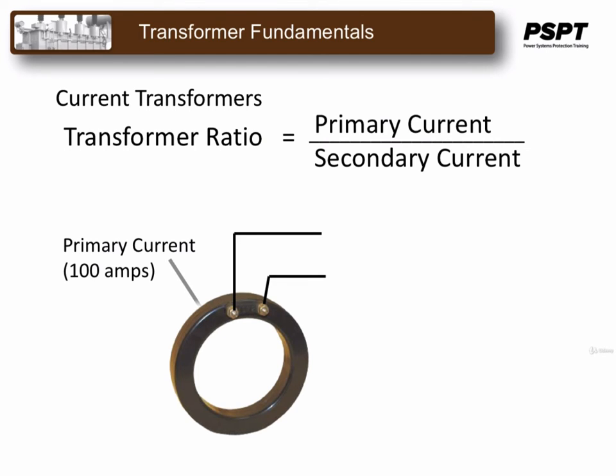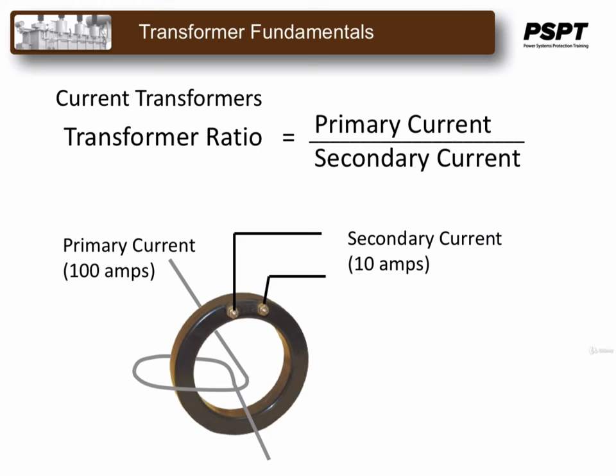For the same CT, what would happen if the primary was looped back and then fed through the CT one more time? The CT would see 100 times 2, which is equal to 200 amps, if 100 amps was flowing in the primary. The secondary would then read 20 amps. The transformer ratio would equal 100 to 10, or 10 to 1. This, of course, exceeds the rating of the secondary. However, this is only used if the primary current is too low for the meter reading. In other words, the primary is usually well below 100 amps, making the secondary current well within limits.